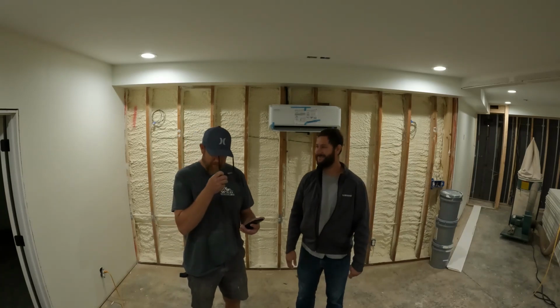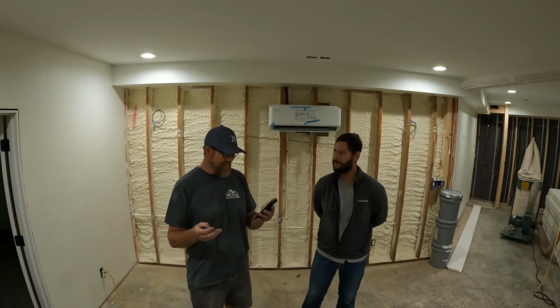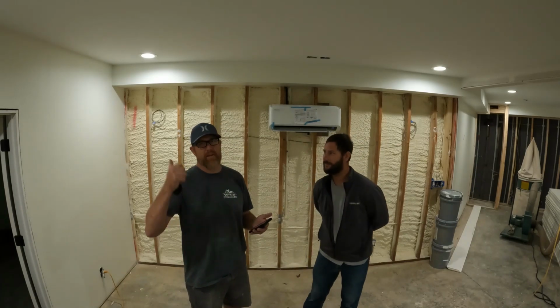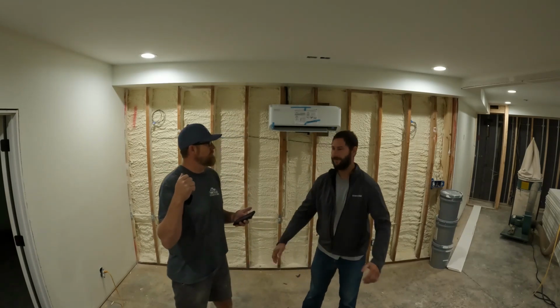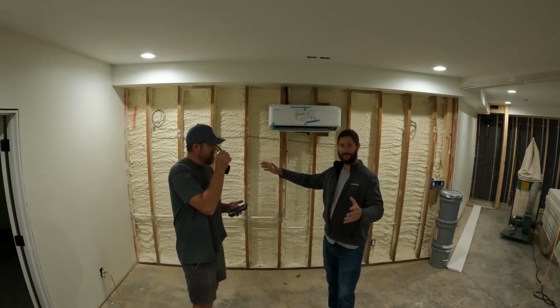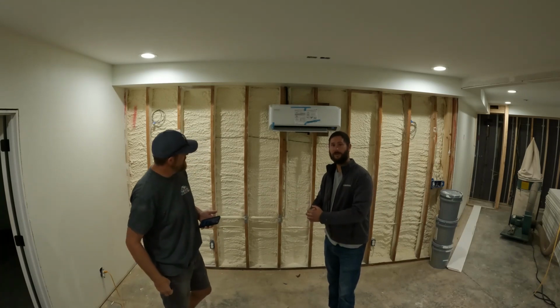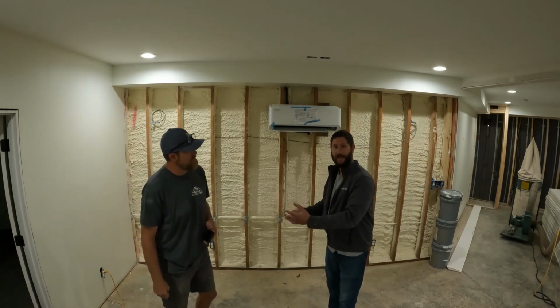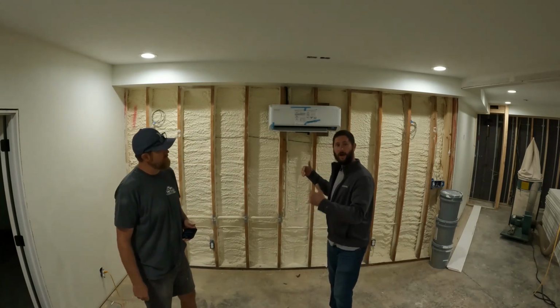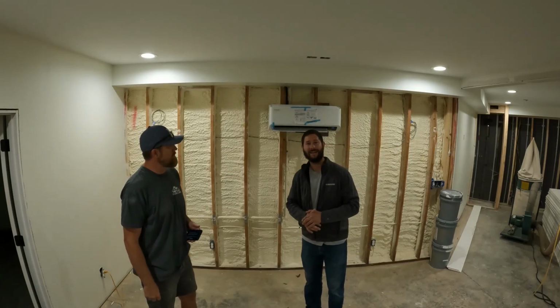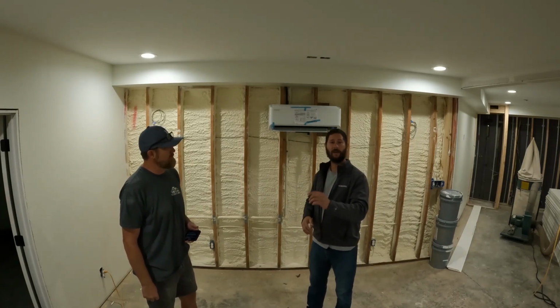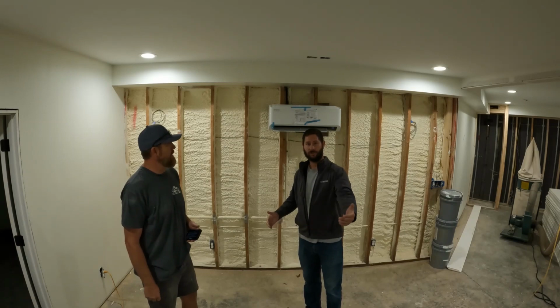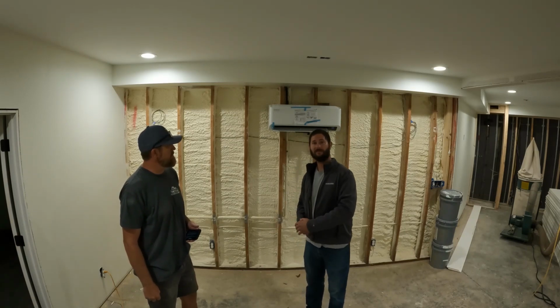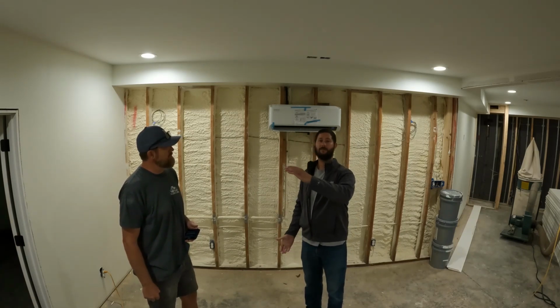Let me ask another. What is the furthest length you can run a line set from the condensing unit that sits outside? Awesome. Okay, so this is a multi-port condenser outside. It's a multi-zone piece of equipment. That means that you have an outdoor unit, and then you have several indoor heads. On this particular system, you can have line set lengths for a single line set up to 98 feet. That's horizontally. Vertically, you can have a vertical separation of about 50 foot.